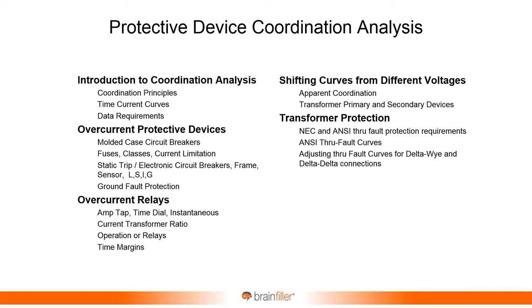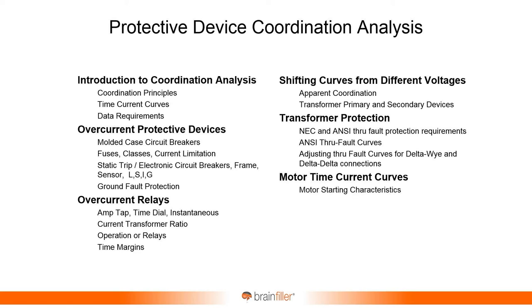There's also an issue when protecting a transformer that the transformer winding connections can create. For example, with a delta-wye grounded transformer protected using the ANSI through-fault curve, there are special considerations you need to make — otherwise a transformer you thought was protected really is not protected. We're also going to take a look at motor time current curves and use those to evaluate motor starting characteristics and the protection for motors.